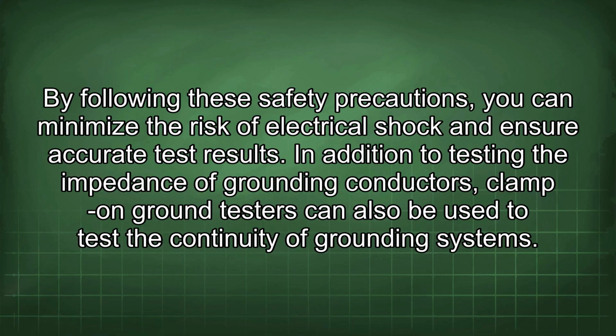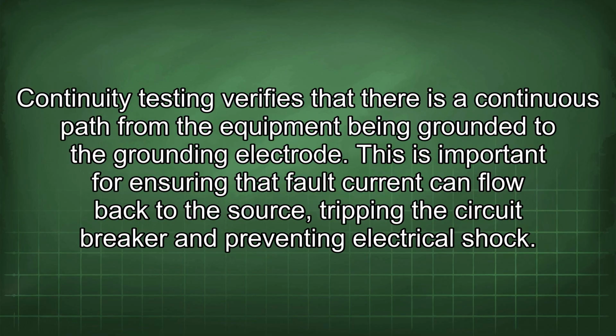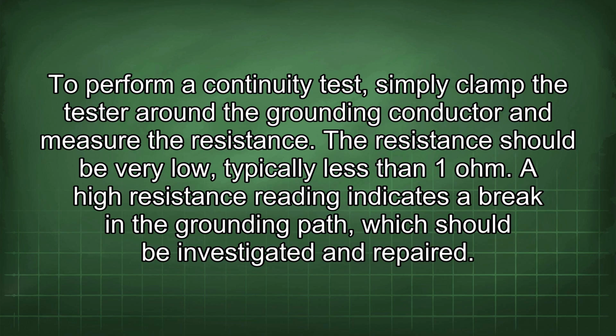In addition to testing the impedance of grounding conductors, clamp-on ground testers can also be used to test the continuity of grounding systems. Continuity testing verifies that there is a continuous path from the equipment being grounded to the grounding electrode. This is important for ensuring that fault current can flow back to the source, tripping the circuit breaker and preventing electrical shock. To perform a continuity test, simply clamp the tester around the grounding conductor and measure the resistance. The resistance should be very low, typically less than 1 ohm. A high resistance reading indicates a break in the grounding path, which should be investigated and repaired.